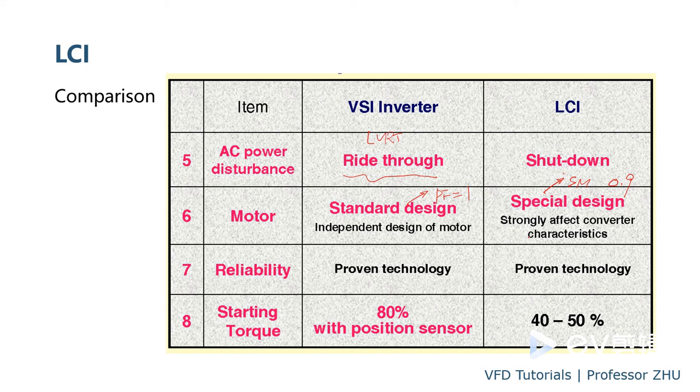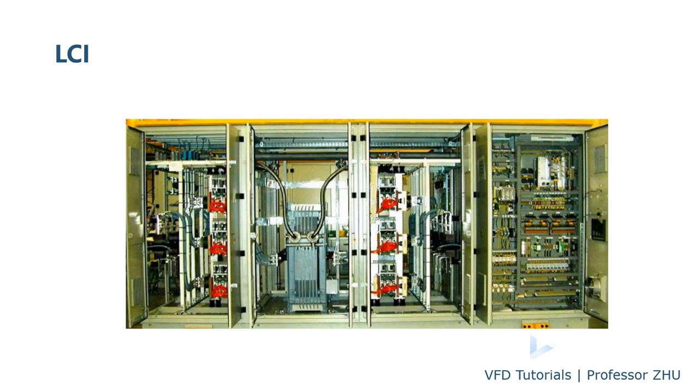And the reliability, both of them are reliable. And for the starting torque, LCI because of the harmonic and torque ripple, normally it's 40 to 50 percent. But for the VSI, it's much higher. And here is a typical outlook of the LCI drive. Here is a rectifier, AC to DC, reactor on the DC, DC to AC, and control.